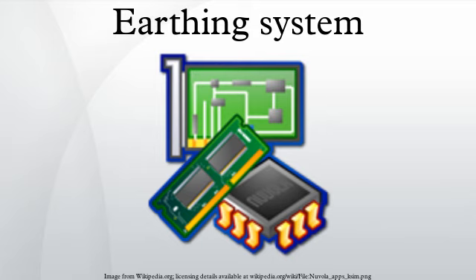Low-voltage systems: in low-voltage distribution networks, which distribute the electric power to the widest class of end users, the main concern for design of earthing systems is safety of consumers who use the electric appliances and their protection against electric shocks. The earthing system, in combination with protective devices such as fuses and residual current devices, must ultimately ensure that a person must not come into touch with a metallic object whose potential relative to the person's potential exceeds a safe threshold, typically set at about 50 V.